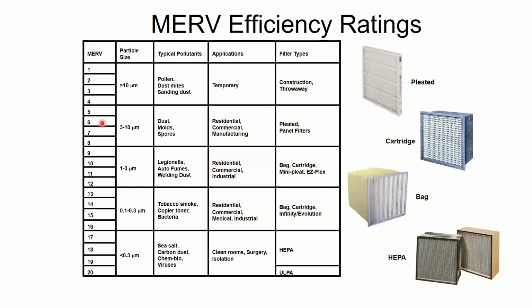If my little COVID buddy is up in the high 0.8, 0.9, almost 1 micron range, now I need to be down over here to have a shot at catching him. I'm not going to catch a COVID virus, or any virus for that matter, with a MERV 10 or MERV 12 filter. That's not going to happen. ASHRAE is recommending, at an absolute minimum related to this COVID pandemic, that you use MERV 13 filters in all of your air handling systems. And if you can, put a MERV 14 in, because that's probably going to catch the COVID. MERV 13, kind of dicey on whether it's going to get it or not. So MERV 14 is the recommendation from ASHRAE. MERV 13 is the bare minimum if you want to start reopening your businesses.